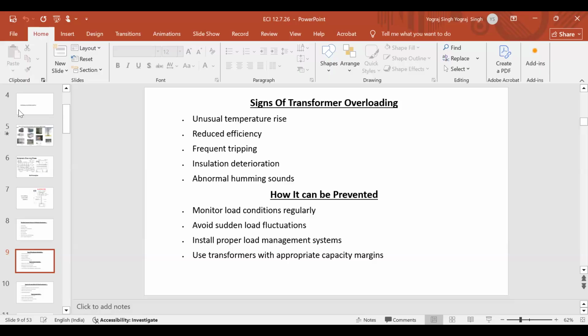Suppose in one of the phases, you provide a load in such a manner that one complete phase comes down to about 20% of the load. So load fluctuation should not be allowed much. Load management system is very important. When you distribute the power, it is either in the form of overhead lines or in the form of underground cables. In overhead lines, by suitably altering the jumpers, you can reach uniformity of load. In the case of underground cables, the same thing can be done in the feeder pillar box, where the jumpers can be changed, phases can be changed. Now, capacity, I'll come to this, there is a slide on this. It will come, what is the capacity to which this transformer should be loaded.